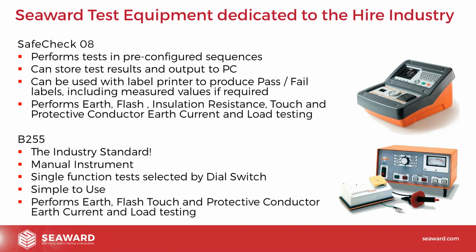So essentially in our Seaward range of equipment, we have two products that are absolutely dedicated and manufactured in accordance with guidance for the hire industry. We have our SafeCheck 8 instrument. This is the more modern of the two instruments. It performs tests sequentially, so you can pre-configure test sequences, and that sequence will run through a list of tests with all the limits and times defined by you, and makes things nice and easy for the operators.